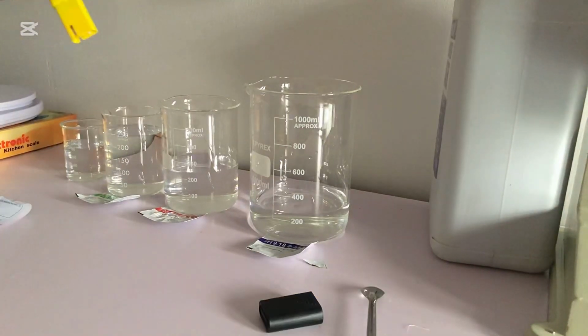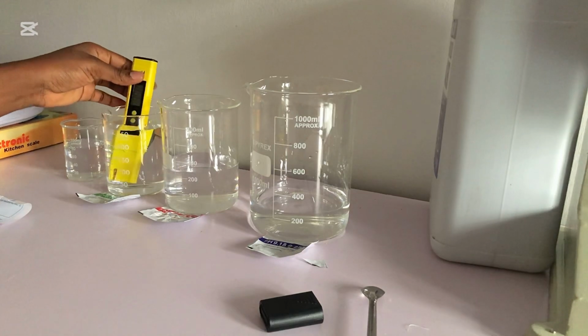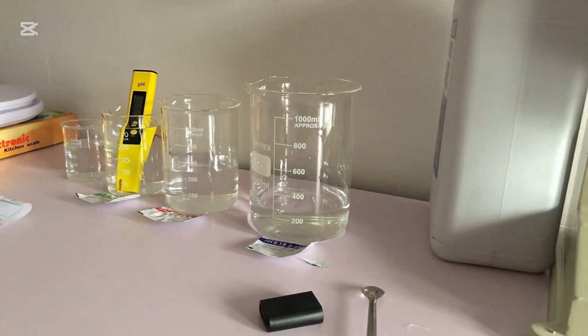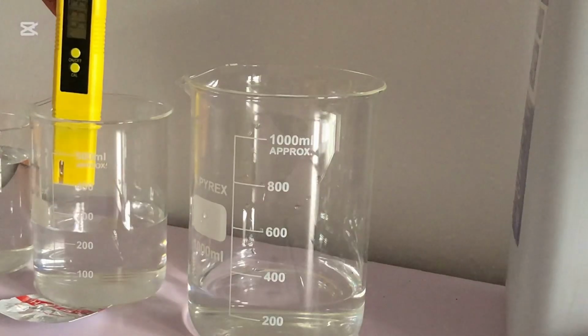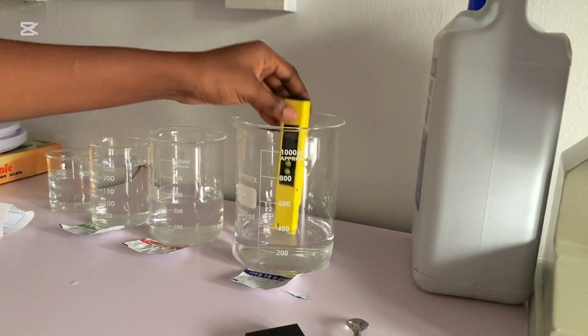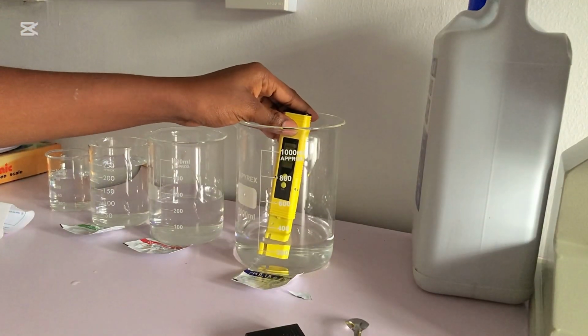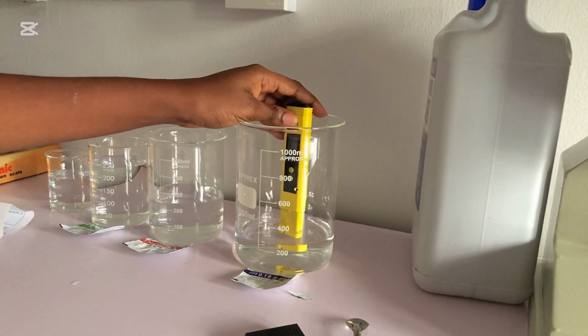So the next step is to place your pH meter into the first pH solution, which is 6.86, and wait until the display is stable, that is the pH on the pH meter corresponds with the buffer solution. Then press the calibration button for 5 seconds and release it. The display will start flashing 6.86, and you wait until that display stops flashing.